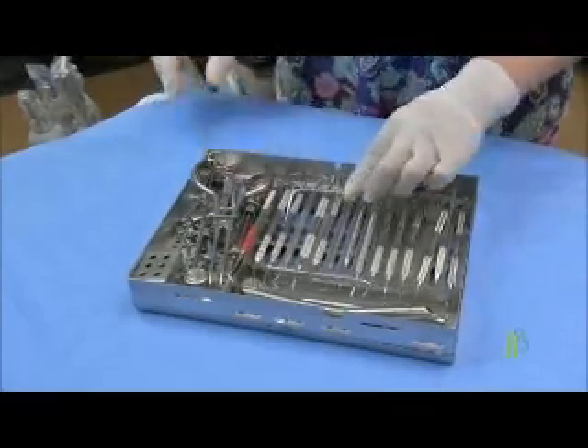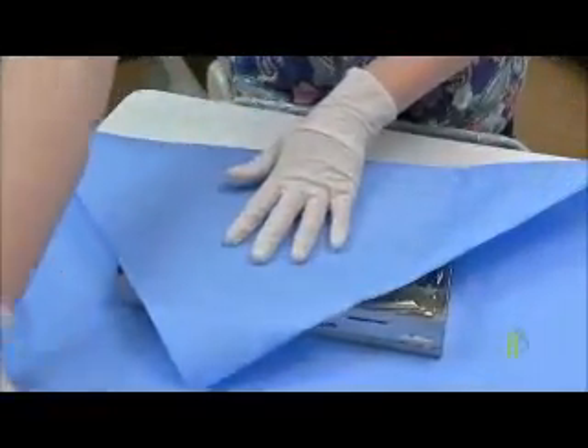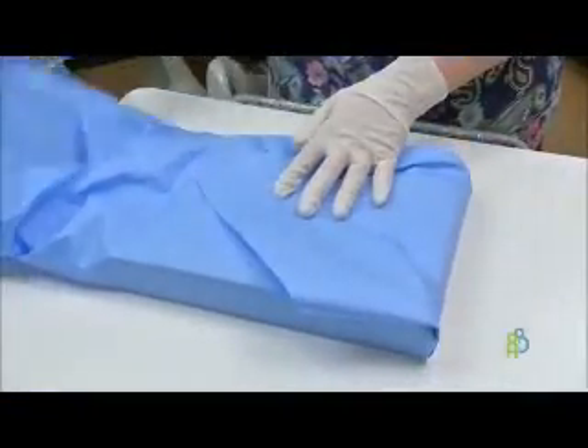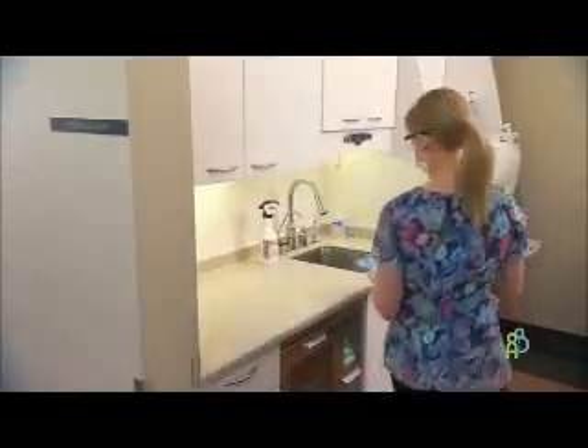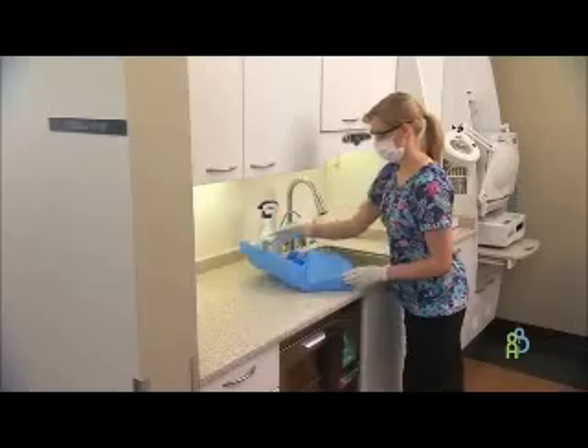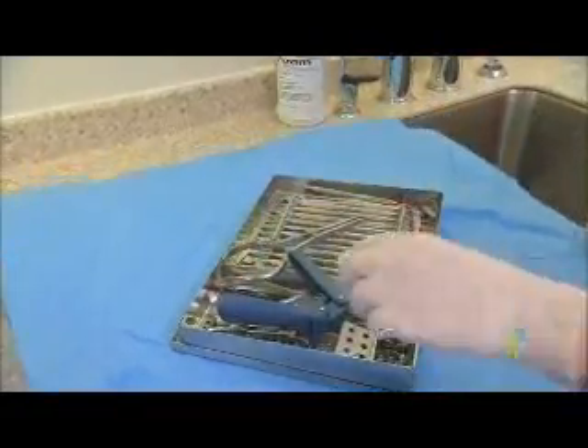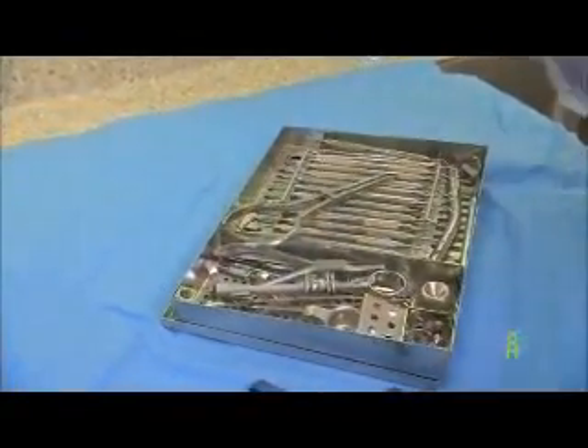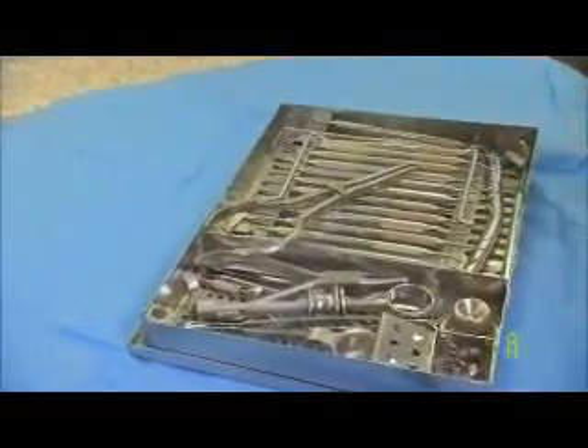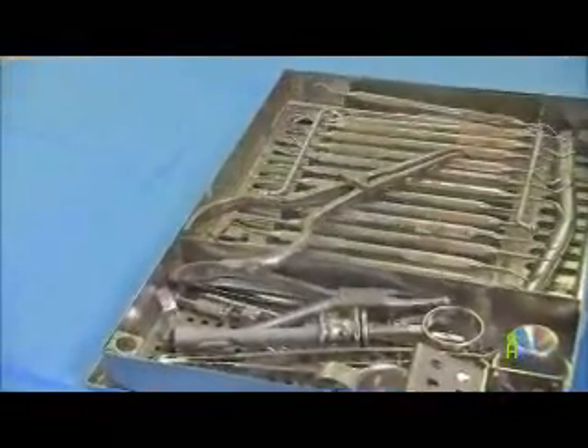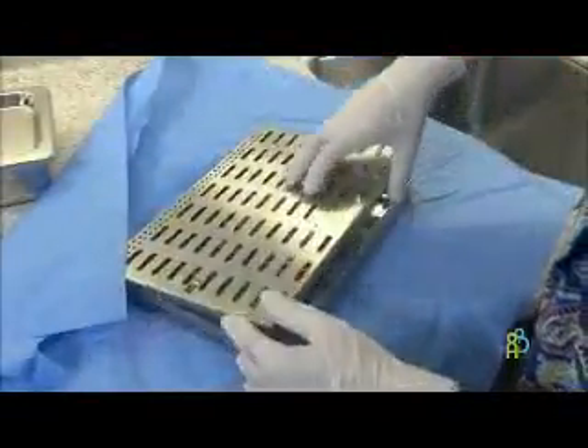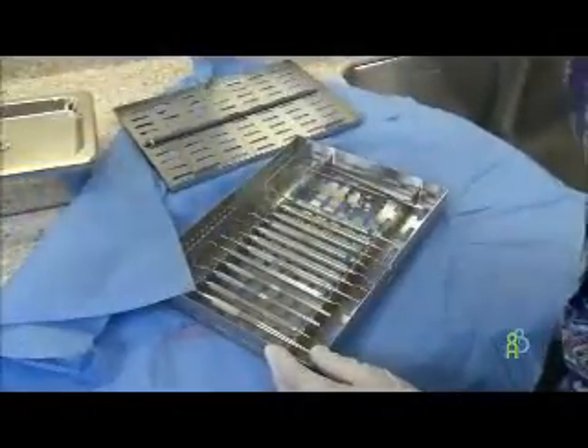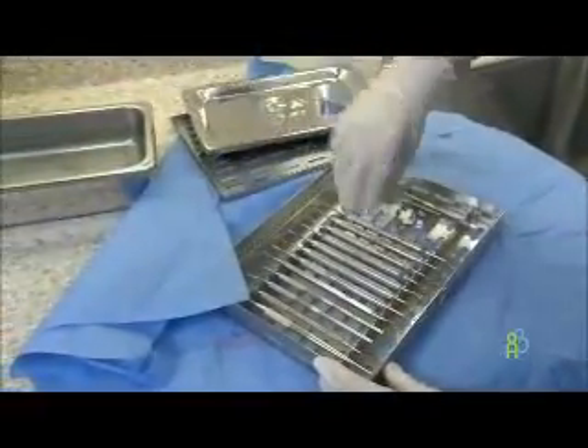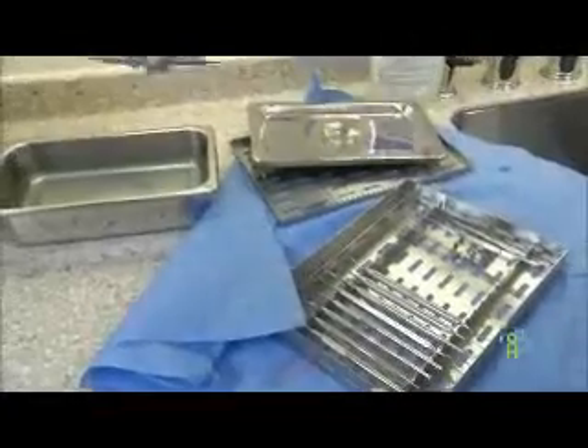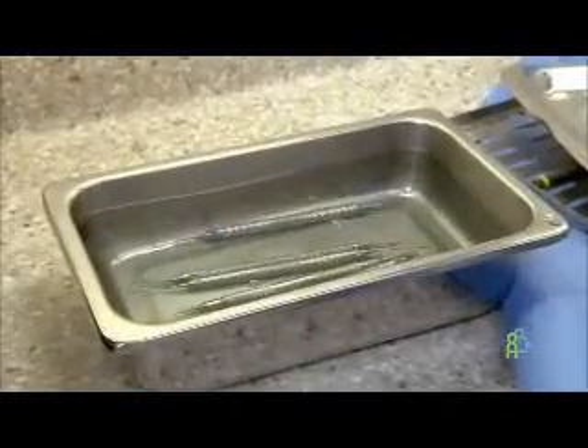Following initial cleanup, trays should be covered and transported to the reprocessing area's designated soil receiving area. If you're not able to clean the used devices immediately, they should be kept moist until reprocessing can be completed. This can be achieved by covering devices with a foam or gel product intended for this use, or placing them in a holding solution intended for this use. Saline should never be used as a holding solution, as it will corrode instruments.